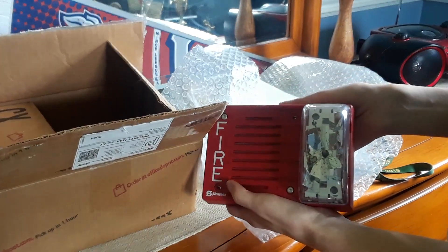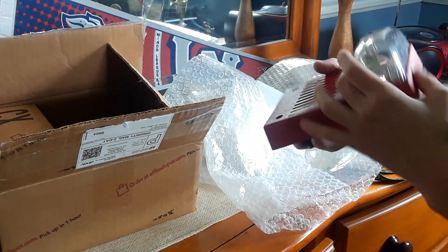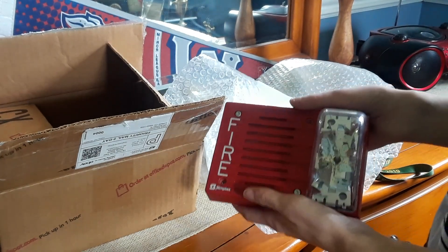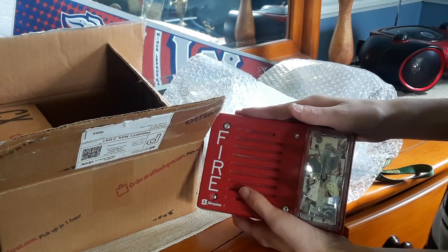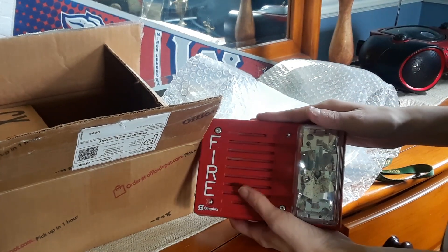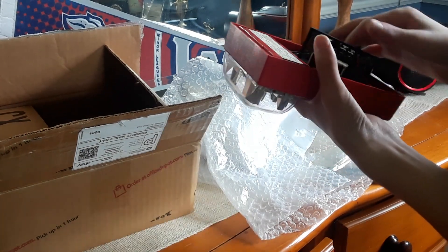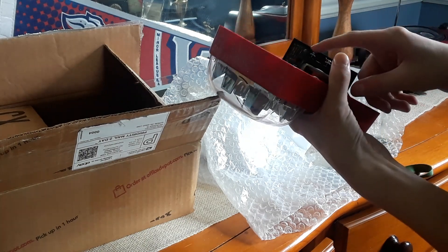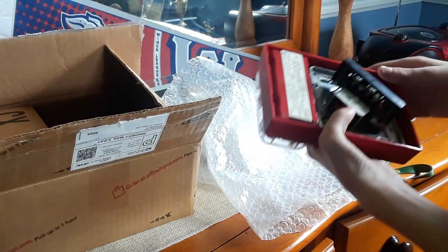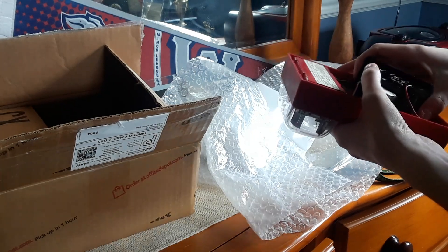4903-9219. It has a mechanical horn. These are the ones that they use in school. It's different between the 19 and the 17 and the 15 in that the 19 has a visual candela module, which means I need to clean this thing off. This thing has the power to change candela level. Now I'm not sure how to do that at the moment. This is a problem — this is a four-wired alarm but there's a screw missing.